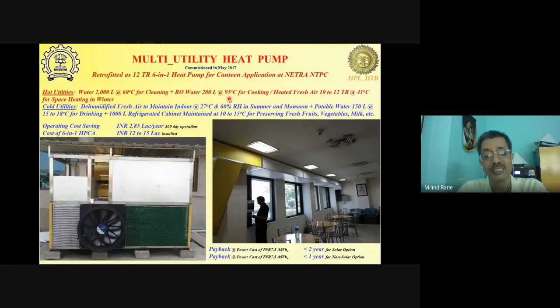So if you put rice in this, you don't need to heat it up at all. Your rice will get cooked without having to heat it further. This was also used for cooking dal and other, of course, that needed further heating, vegetables and other things. So as you can see here, 6 utilities being generated. Now the common problem in all these type of systems would be that when the cooling is produced or required, you don't need heating. When the hot water for cooking or hot water for cleaning is required at that time, the canteen might not be operating.